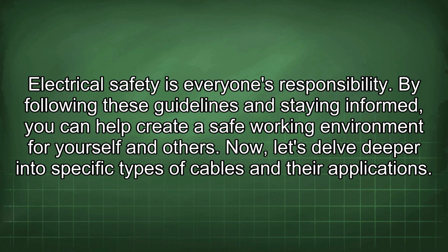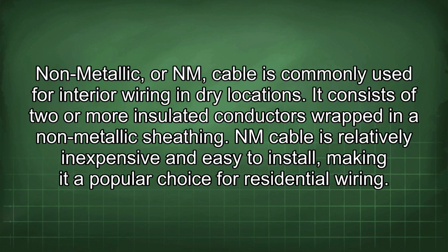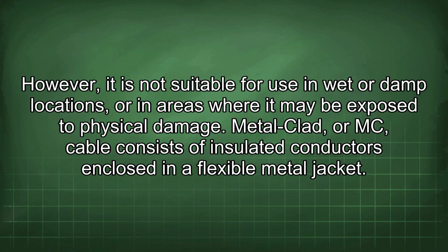Now let's delve deeper into specific types of cables and their applications. Non-metallic, or NM, cable is commonly used for interior wiring in dry locations. It consists of 2 or more insulated conductors wrapped in a non-metallic sheathing. NM cable is relatively inexpensive and easy to install, making it a popular choice for residential wiring.